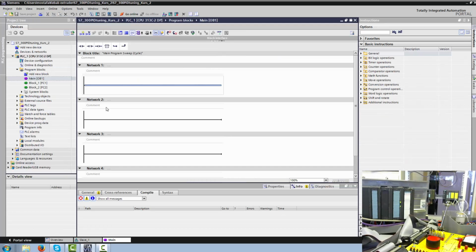Now we will start programming the PID. First of all, you should keep in mind that you cannot directly use the data you're reading from the sensor. So you should scale it. I mean, if the temperature of the room is 25, the sensor will read 250. Our sensor, at least, we're using PT100, I suppose. So we have to scale it to have the real temperature.